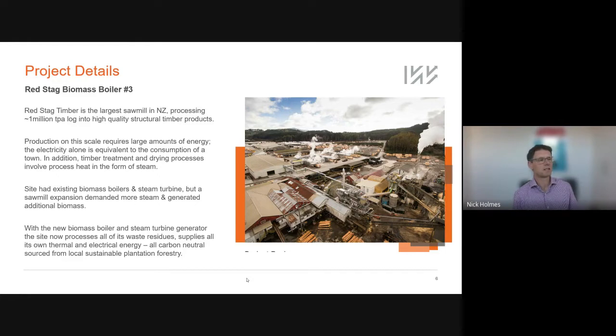At this site, they did have an excess of very wet fuel, so their existing boilers couldn't burn that fuel. That was one of the drivers to utilize a new boiler that would burn 60% moisture fuel. That's incredibly wet. The excess steam produced could then go into a turbine, and there's a bit of cogeneration on site as well.